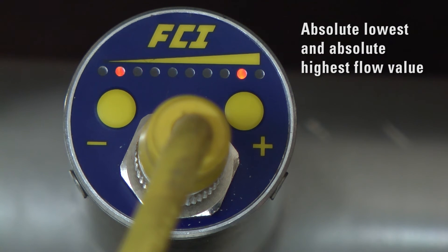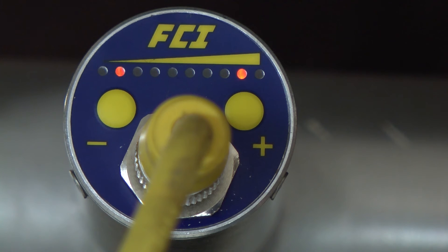Then slowly reduce the flow until zero flow is reached. Setting the low flow down to around 10% will yield more linear results over the entire range, as this zero offset removes a steep portion of the curve.